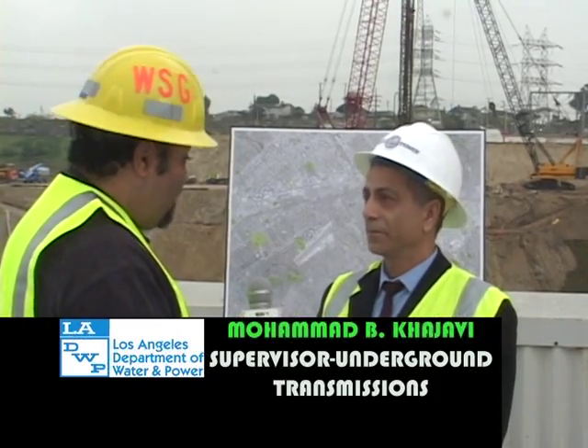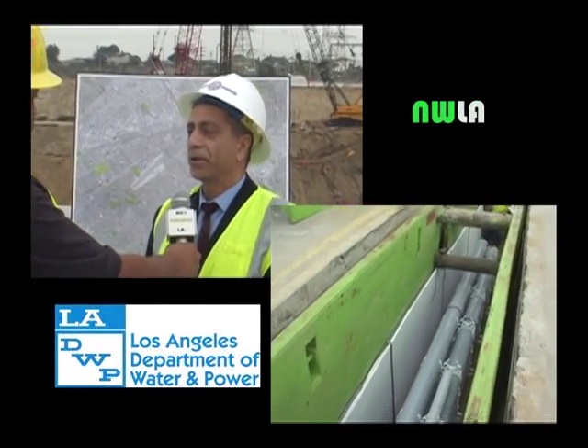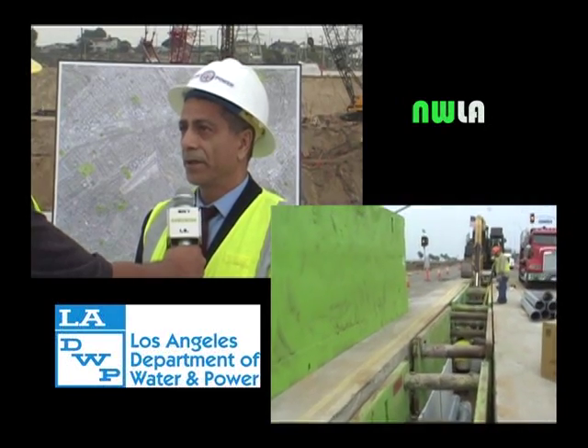I'm here with Mohamed Kajavi of the Los Angeles Department of Water and Power, the head of underground transmissions for the department. To take the power generated at Scattergood, we have to transmit it to distribution points along the city. The department has chosen to go underground cabling as opposed to overhead, for its reliability, aesthetic quality, and convenience to city residents. The underground transmission system is basically a system of three cables — because it's three-phase — and this one set of cables is good enough to carry enough energy to power 600,000 homes.